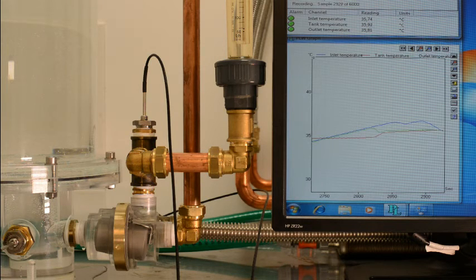And there you see that the valve is now switched position before the inlet temperature actually reaches the tank temperature. So this gives you the 100% guarantee that heat is never drawn from the tank, and heat can only be added to the tank when using the thermo-differential bypass valve.